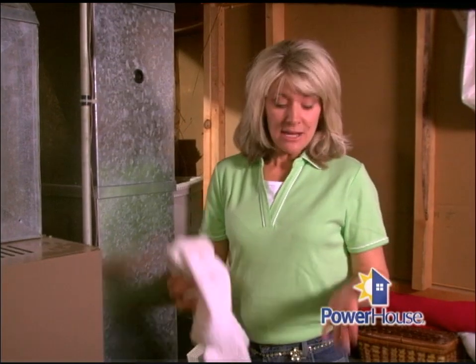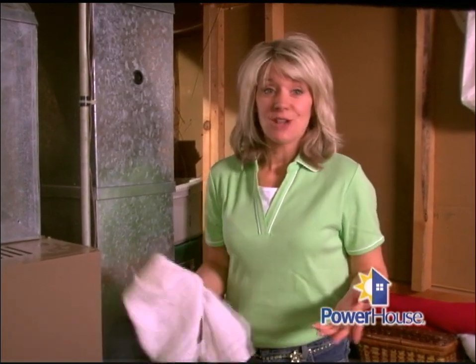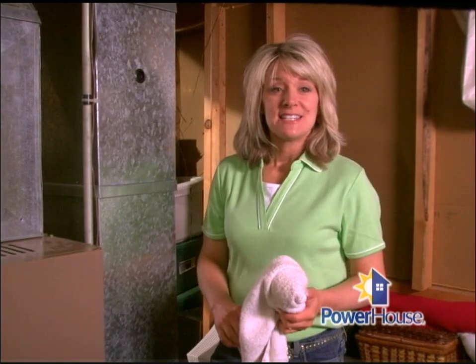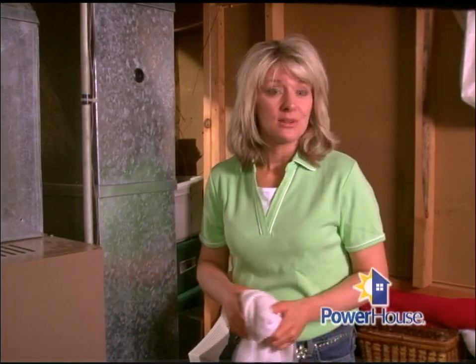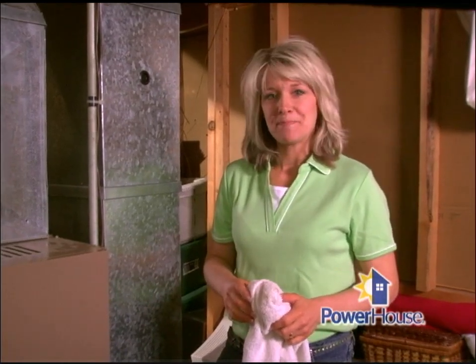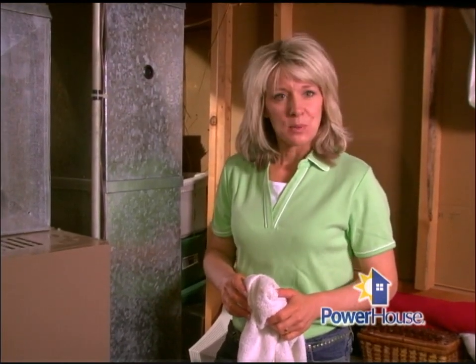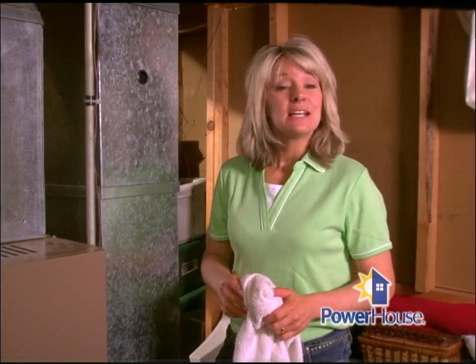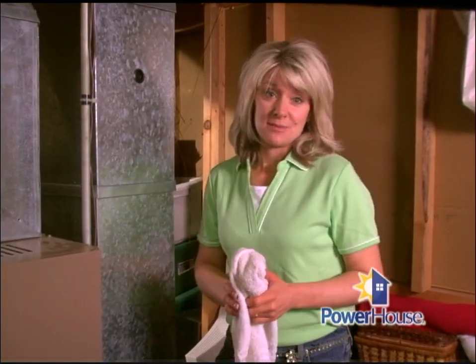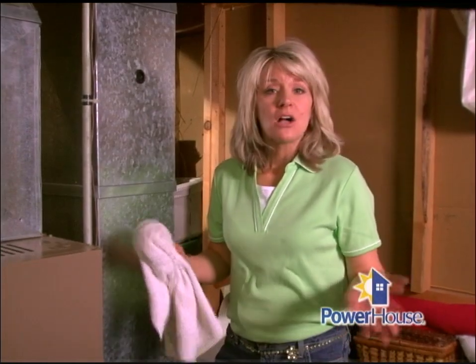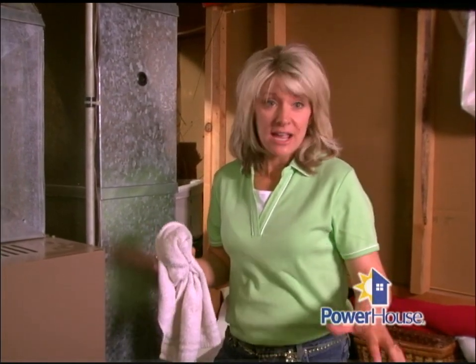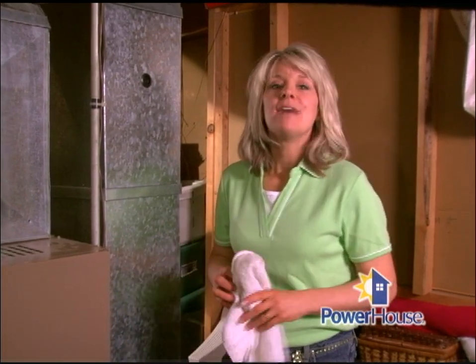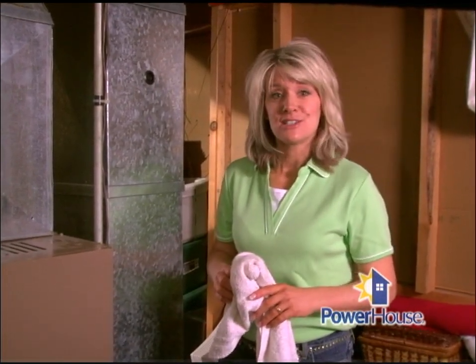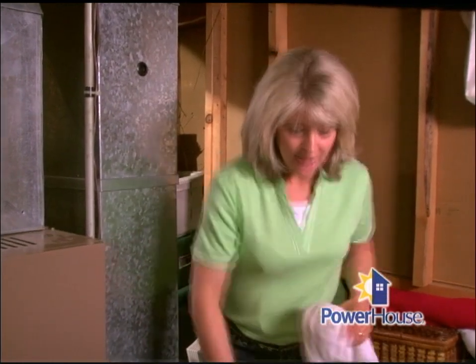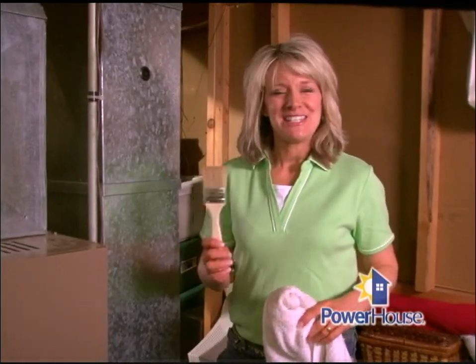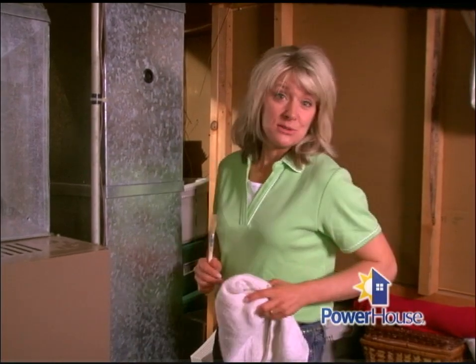The mastic we're applying here, however, is water-based. Unlike solvent-based mastic, water-based mastic contains vinyl, acrylic, or latex components that don't require harsh chemicals for cleanup. Water-based mastic is non-flammable, it produces no harmful fumes, and it can be used on indoor and outdoor duct systems. You can apply it with a trowel, a caulking gun, or by hand, but if you do use your hands to scoop the mastic out, make sure you wear heavy rubber gloves that won't tear if pressed against a sharp edge of sheet metal. Now, you may find that using a cheap paintbrush is the easiest way to apply mastic, and that's what we'll be using today.